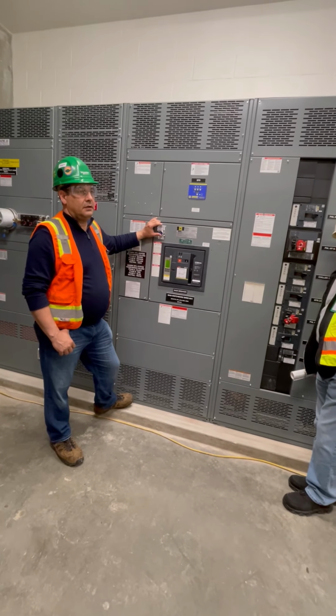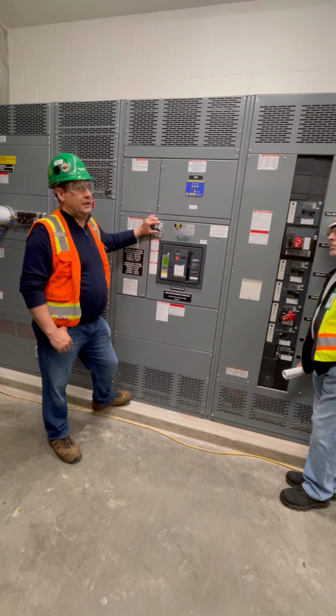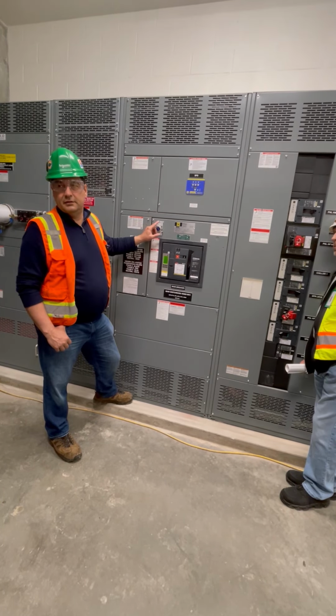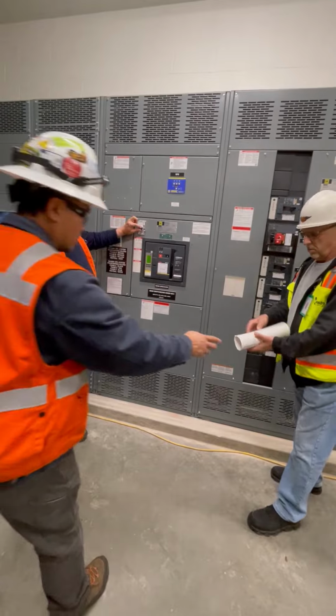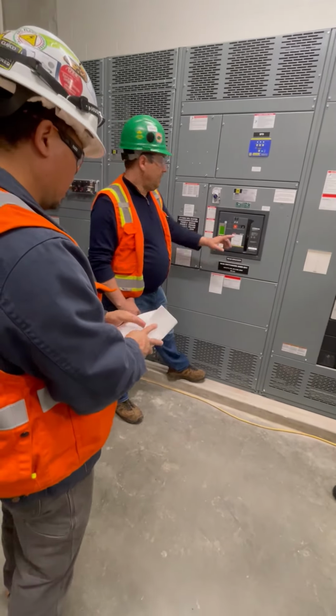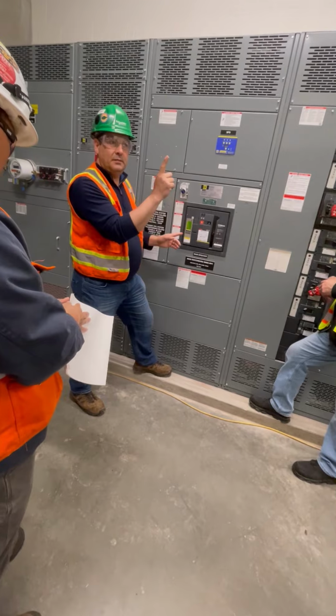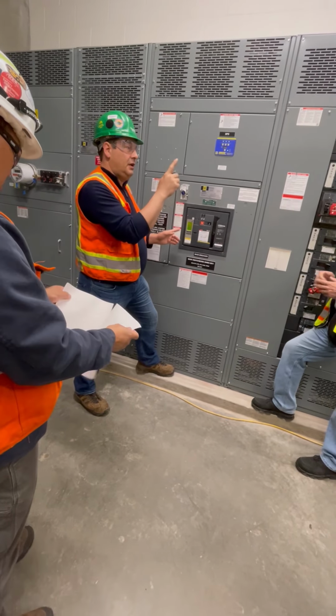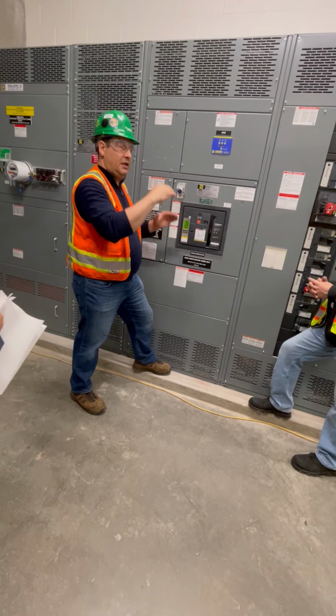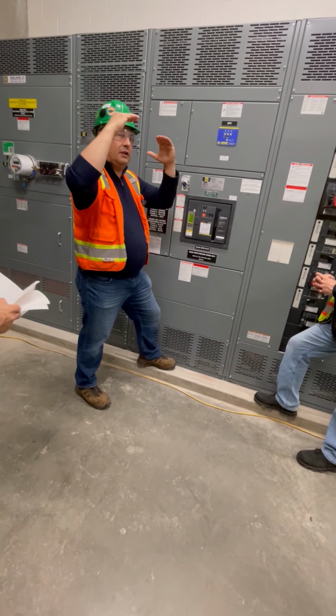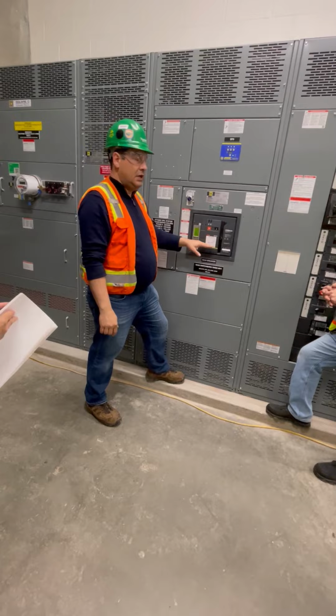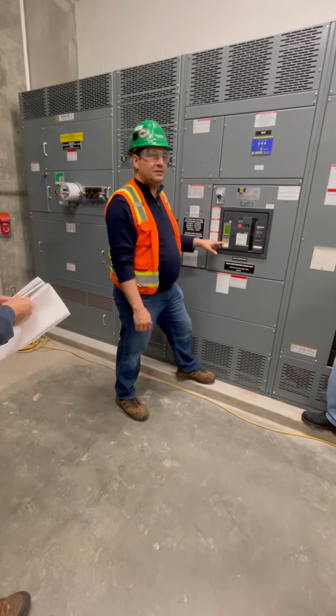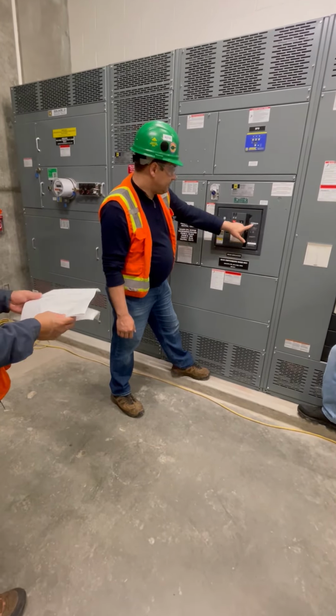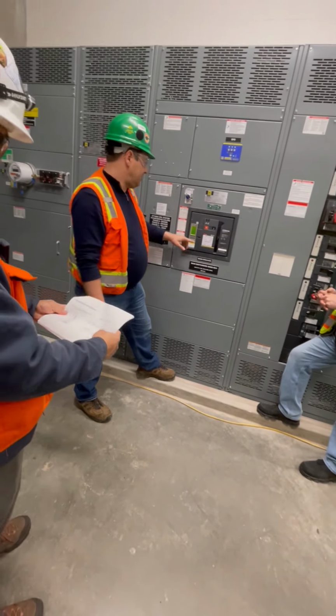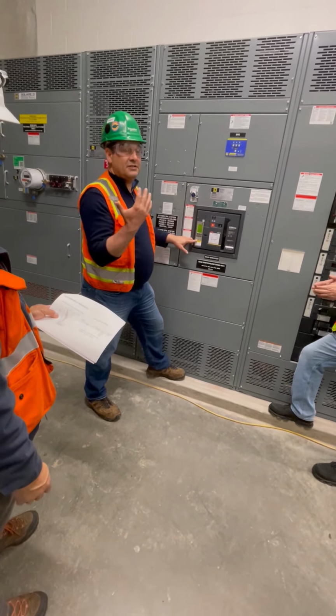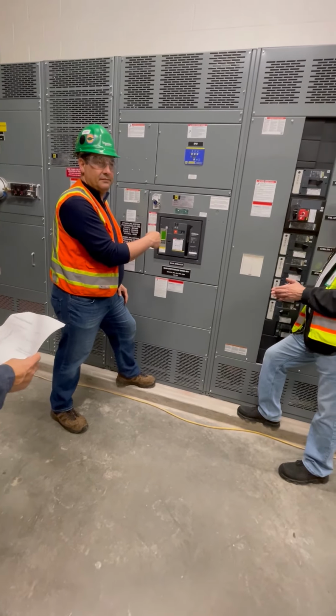That reduces the ampacity also? Not the ampacity, it's the arc flash. Okay. It reduces it. Am I correct on that? Yeah, let me take a look. It doesn't reduce the ampacity because, remember when I said long time dictates the ampacity of the breaker? It reduces short time and instantaneous. It reduces the magnitude of the fault current that this breaker will allow to go through. So if this breaker was set at 10 times instantaneous, and it's a 3,000 amp breaker, that means on instantaneous it's letting 30,000 amps go through before this breaker trips, okay?